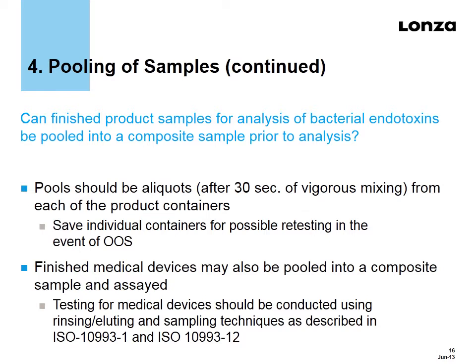The document states that pools should be aliquots made up after 30 seconds of vigorous mixing from each of the product containers, and that the individual containers should be retained for possible retesting in the event of an out of specification result. Finished medical devices may also be pooled into a composite sample and assayed, and testing for medical devices should be conducted using the rinsing, eluting, and sampling techniques described in ISO 10993-1 and ISO 10993-12.